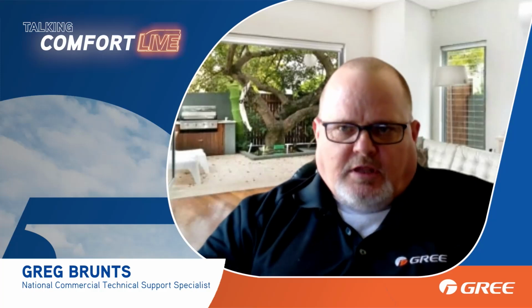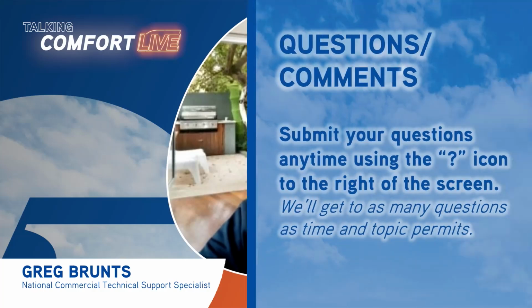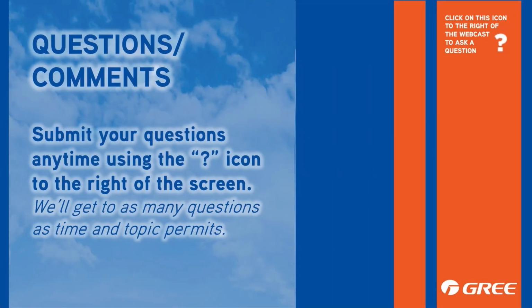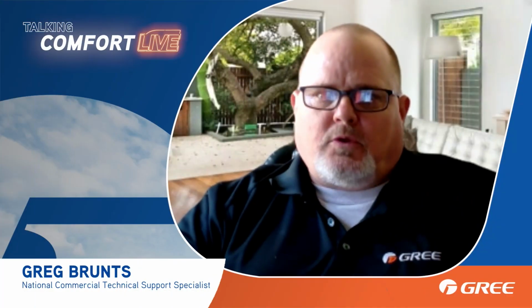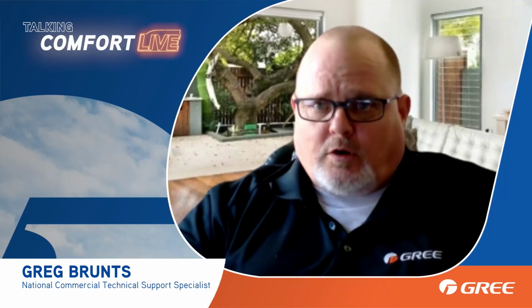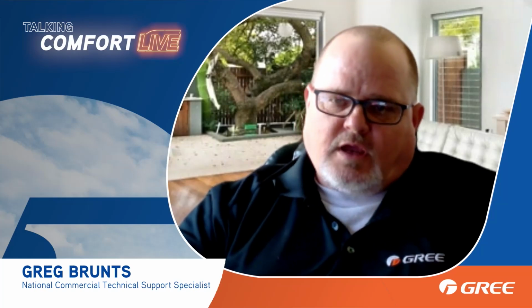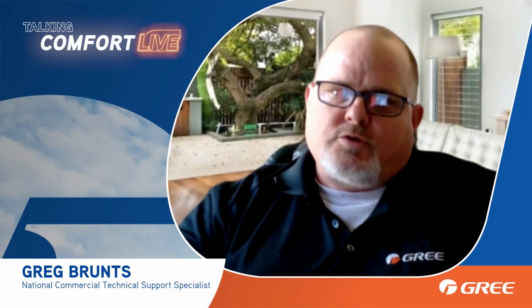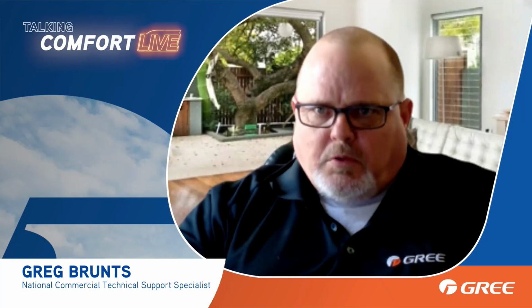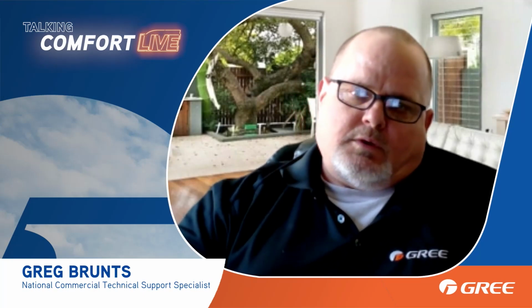Secondly, you have a couple different options with humidity, dehumidification, I should say. Okay. Just like the previous FLEXX, you still have an energy savings mode set of dip switches. They are SA1, 3, and 4. If you set that unit to energy savings mode, you're going to force longer run times, which is going to give you better dehumidification. Then on top of that, you have the DH terminal in there. So if your thermostat is capable of giving a 24-volt output for dehumidification mode, and we send 24 volts to the DH terminal on the air handler, it will slow the blower down and give you a better dehumidification mode.